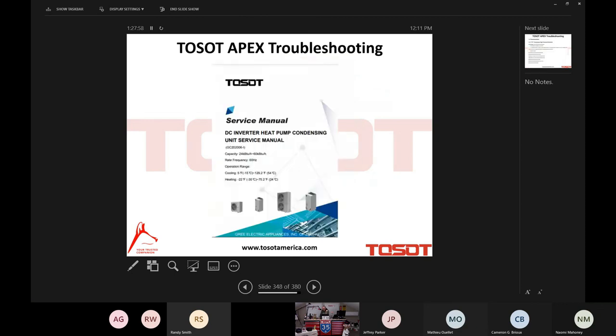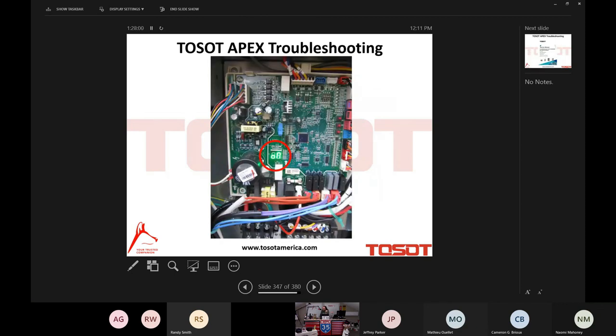And again, when the system is running beautifully and everything is hunky-dory and everything is happy, it's hard to see there, but that actually says on. What the LED screen is showing is on. Hard to take a still picture of it because it has a pulsation to it, and the frames per second of the camera does not match the pulse of the LED, which is very typical. So it's just hard to get a still picture of it, but it actually says on.